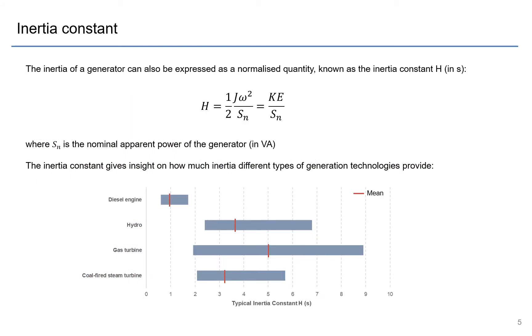We previously described the inertia of a generator as kinetic energy in terms of joules or megawatt seconds, but we can also normalize this inertia by getting the kinetic energy and dividing by its nominal apparent power of that generating unit. This is known as the inertia constant H. Inertia constant is useful to give an insight on how different generation technologies provide different levels of inertia.